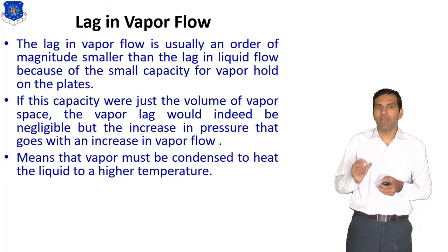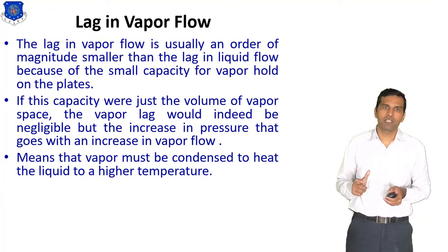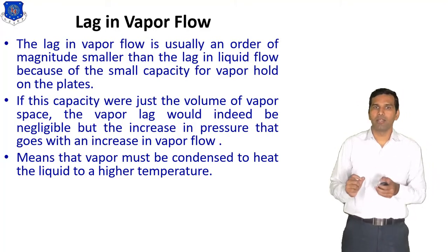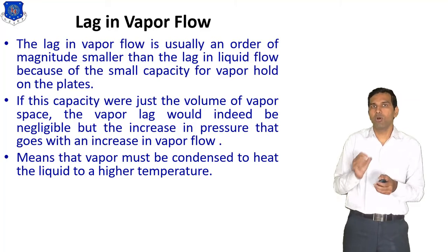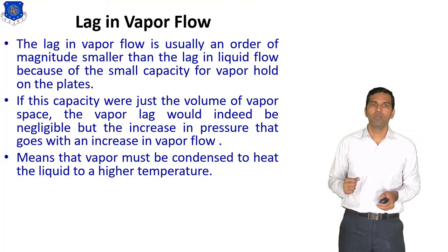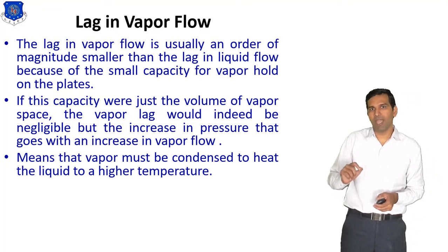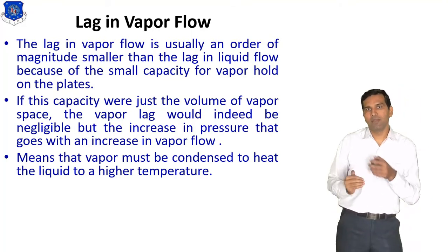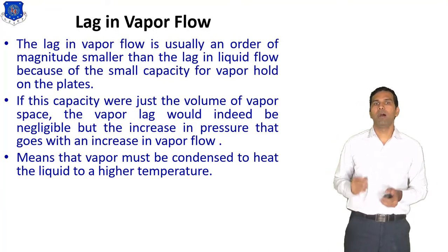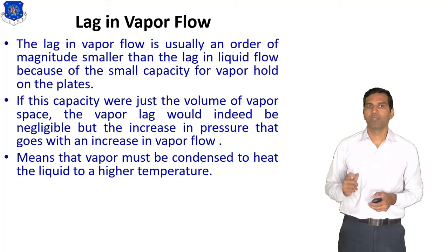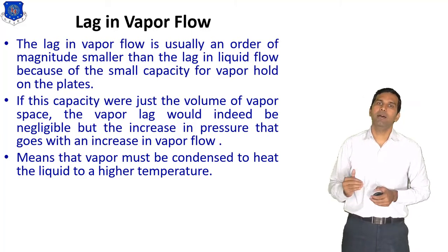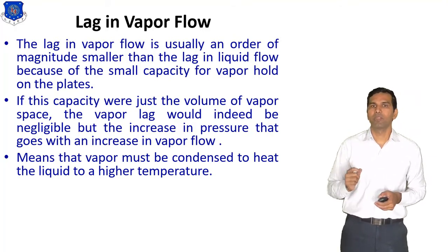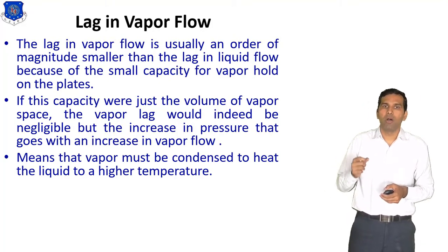If the capacity were just the volume of vapor space, the vapor lag would indeed be negligible, but the increase in pressure that goes with increase in the vapor flow means that the vapor must be condensed to heat the liquid to a higher temperature.